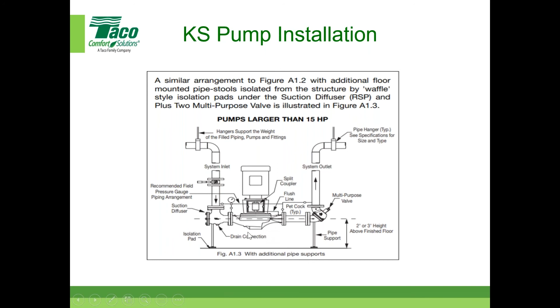It's not mounted to the floor here, so you can clean around it and save some space. That's another reason why some people look at these KV and KES pumps, or vertical inline pumps - there's a good possibility they save space in the mechanical room, and space is money. Maybe you could put three other pieces of equipment in there instead of giving room for maintenance and walking around it. Some stuff to consider there.